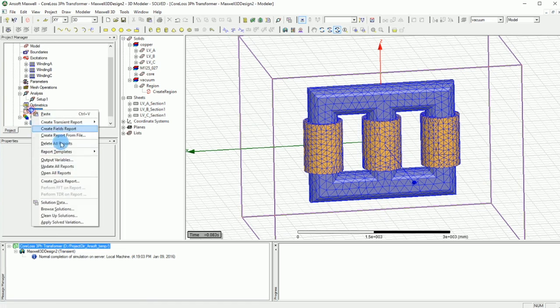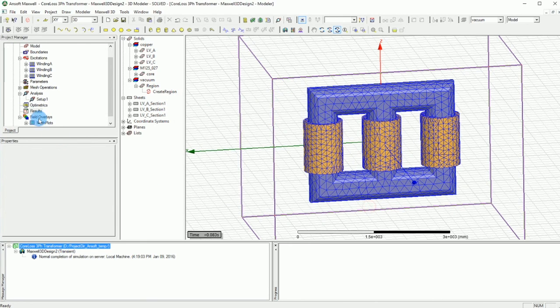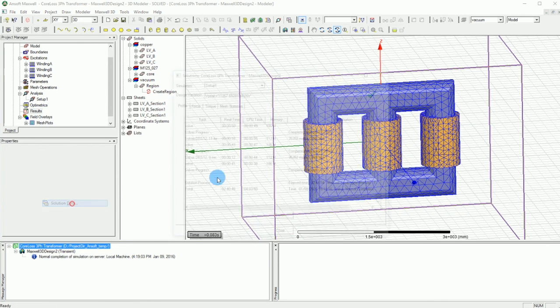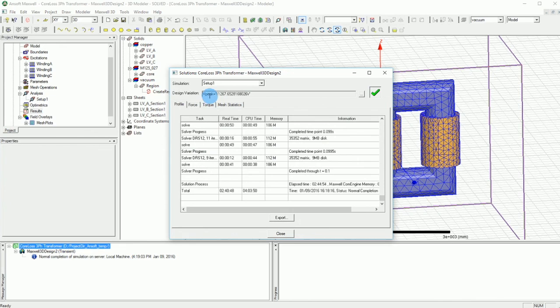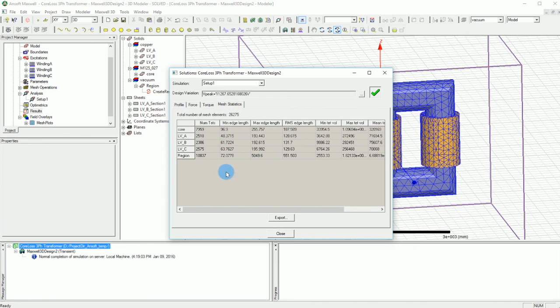The next thing is to check the setup. Go to Results and then Browse Solutions — we do have a solution, which is a good thing. Sometimes you come back and see nothing has been solved and it just crashed without you knowing. Also, when you right-click on Results and go to Solution Data, you can see a check mark next to the Vpeak variable. Remember, Vpeak was a design variable, which is why it appears as a design variation. You can also see how long the simulation took to run. Since we had no force or torque matrices, those two tabs have no information, and the last tab shows mesh quality.